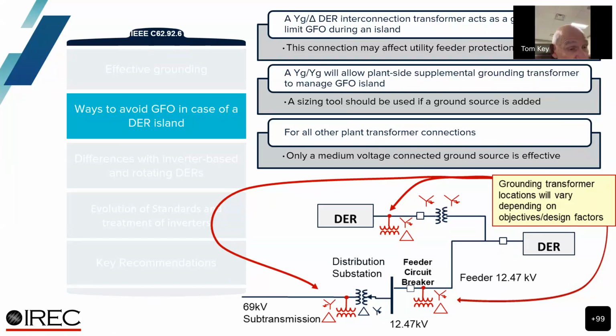Okay, so back to the topic at hand. The transformer connection matters as far as this idea of effective grounding, and again, effective grounding meaning holding that voltage down to a level that the system is able to withstand. So there's quite a difference between inverters and synchronous machines. That's one of the important points of what we've been working on.